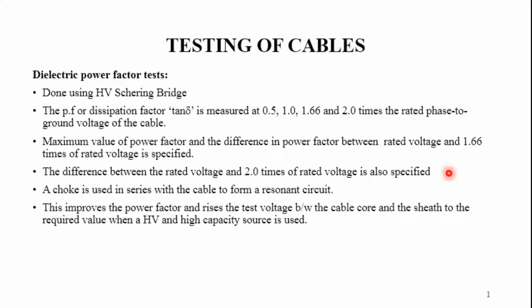Sometimes it is difficult to supply the charging volt amperes of the cable from the available source. In such cases, a choke is used in series with the cable to form a resonance circuit. Using this improves the power factor and raises the test voltage between the cable core and the sheath to the required value when a high voltage and high capacity source is required. So in those cases we can use choke coils.